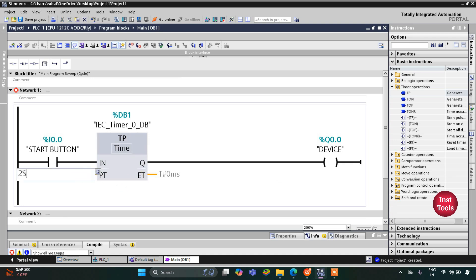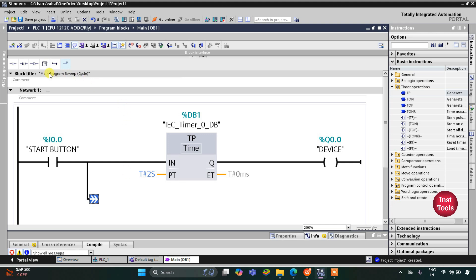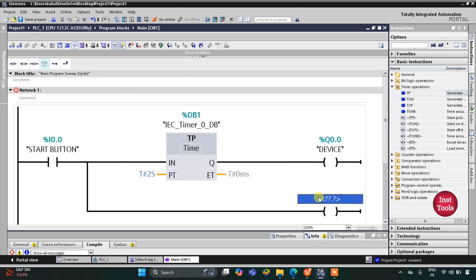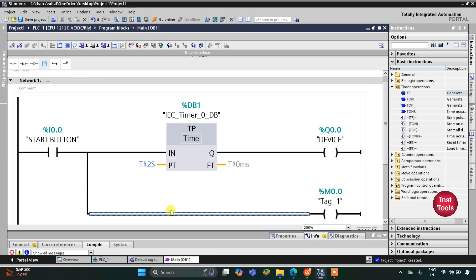I will write 2S, meaning two seconds, as the preset value for the TP timer. When the start button is turned on, the device turns on and will remain on for two seconds, then stop. To keep it off for 10 seconds, I will open a branch and add a coil — a memory bit M0.0. This memory bit will turn on after 10 seconds when the device is turned off.